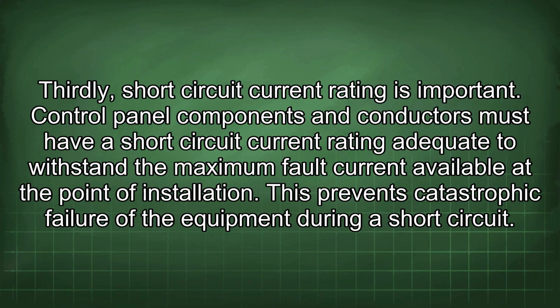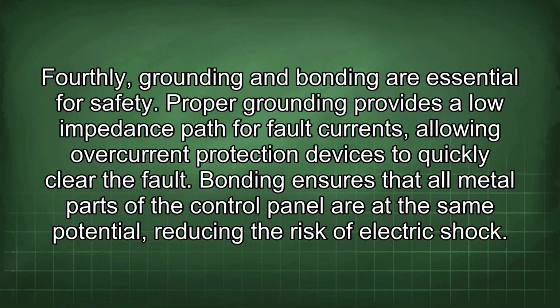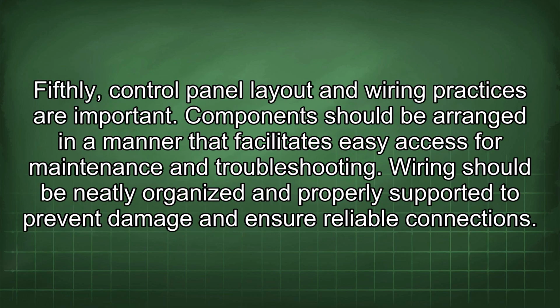Control panel components and conductors must have a short circuit current rating adequate to withstand the maximum fault current available at the point of installation. This prevents catastrophic failure of the equipment during a short circuit. Fourthly, grounding and bonding are essential for safety. Proper grounding provides a low impedance path for fault currents, allowing overcurrent protection devices to quickly clear the fault. Bonding ensures that all metal parts of the control panel are at the same potential, reducing the risk of electric shock. Fifthly, control panel layout and wiring practices are important.